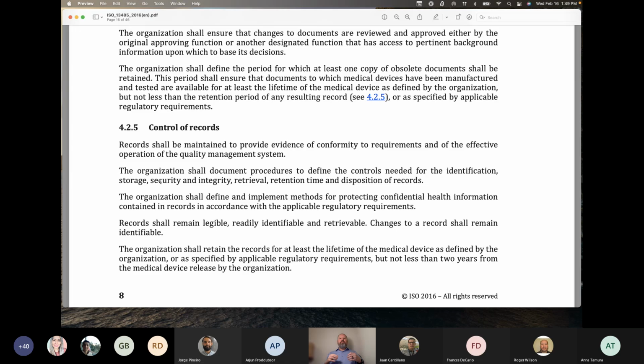Okay, so records specifically are expected to be housed in a secure location, meaning not everybody has access to it. So wherever you keep your records that demonstrate conformity for medical devices to all of the specifications you've lined out, that should be a restricted access location. It should be a locked cabinet. It might be a locked closet, but it is not supposed to be open access. The intent is to prevent people from inadvertently damaging records, losing records, intentionally removing records. It is part of the control of records piece, and that security is the physical control of records, Arjun. Thank you, Brian.